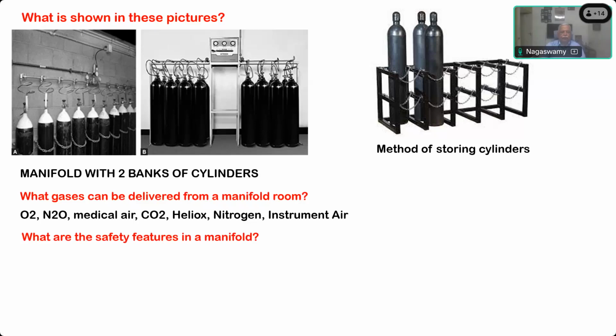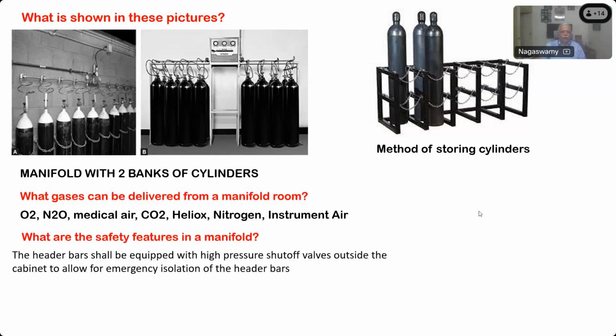Okay. Cut-off valve with pressure indicators, sir. Indicator. Okay. So the header bars will be equipped with high pressure shut-off valves outside the cabinet to allow for emergency isolation of the header bars. So this is called the header bar. This portion where all the cylinders are connected with a strong pipe is called the header bar, and this is called the pressure shut-off valve area.